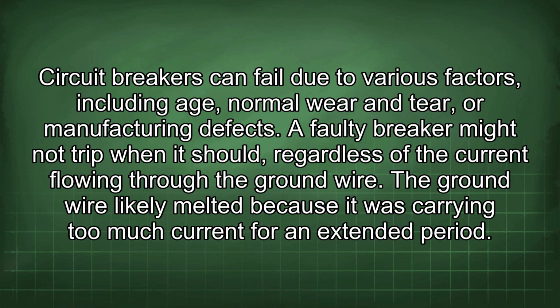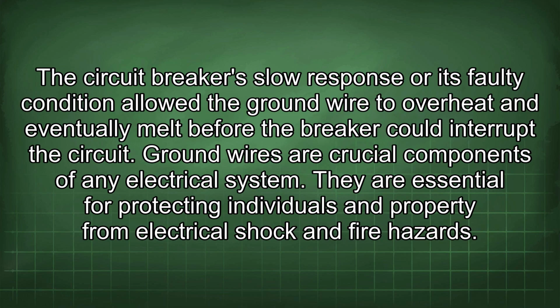The ground wire likely melted because it was carrying too much current for an extended period. The circuit breaker's slow response or its faulty condition allowed the ground wire to overheat and eventually melt before the breaker could interrupt the circuit.